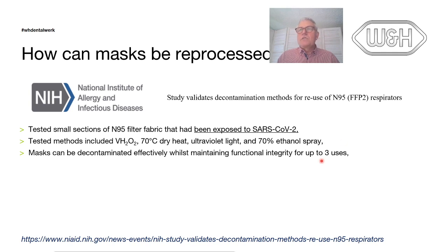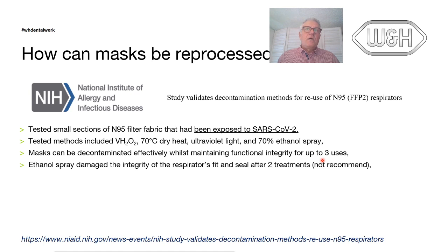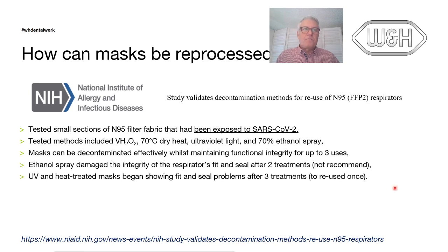They said 2 times reprocessing is okay, so masks can be used 3 times. However, ethanol spray damaged the respirator after 2 treatments, so it's not the number one recommendation. UV and heat show good results, but seal problems after 3 treatments. I will develop this also in a second.